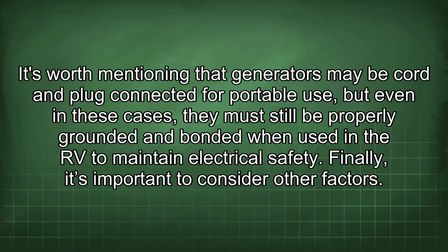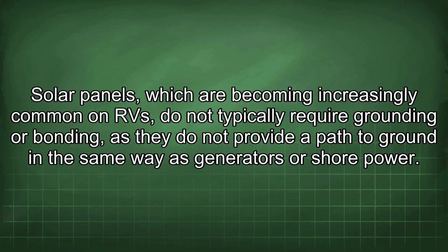It's worth mentioning that generators may be cord and plug connected for portable use, but even in these cases, they must still be properly grounded and bonded when used in the RV to maintain electrical safety. Finally, it's important to consider other factors. Solar panels, which are becoming increasingly common on RVs, do not typically require grounding or bonding, as they do not provide a path to ground in the same way as generators or shore power.